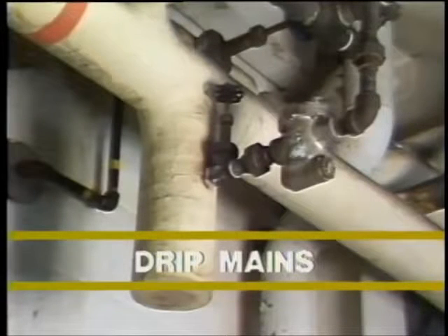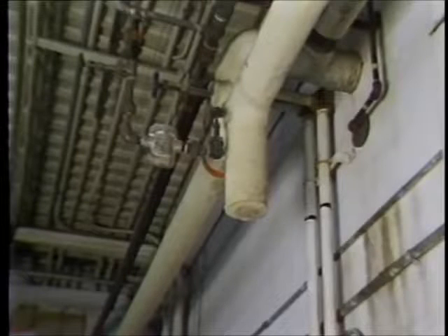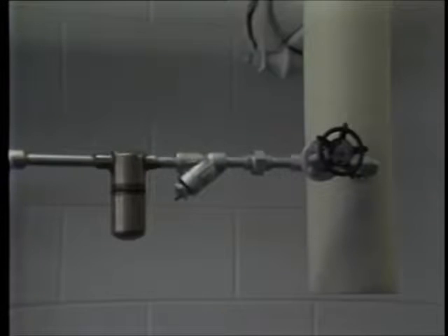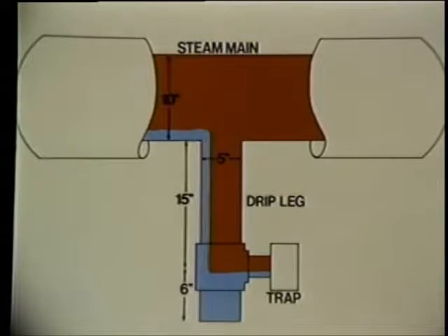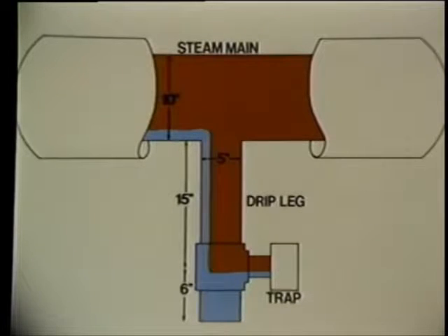Drip legs and drip traps must be installed to automatically drain the mains of condensate. Drip legs divert the condensate from the fast moving steam in the mains and provide a pressure differential during startup, enabling the trap to discharge the condensate to a gravity return. Drip legs should be the same size as the steam mains on pipe sizes up to 4 inches in diameter. Above 4 inches, they should be at least one half the size of the main, but never less than 4 inches. The depth should be at least one and one half times the diameter of the main, but never less than 10 inches.